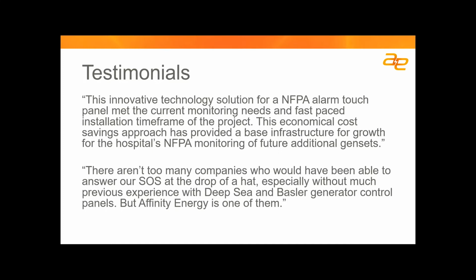The other thing we learned is that even though you have a generator, different control panels can be associated, and there are different approaches to how that generator is controlled. For example, on one installation, as shown in the second testimonial, we had generators with a control panel by a company called Deep Sea, and another control panel by Basler Electric. So if the question is, could you just make this a product someone orders, ships, and connects up—if you know you have brand new generators and know exactly what was programmed in the alarm, that possibility could exist. But in a retrofit environment, there's definitely going to need to be interaction and coordination with the system integrator.